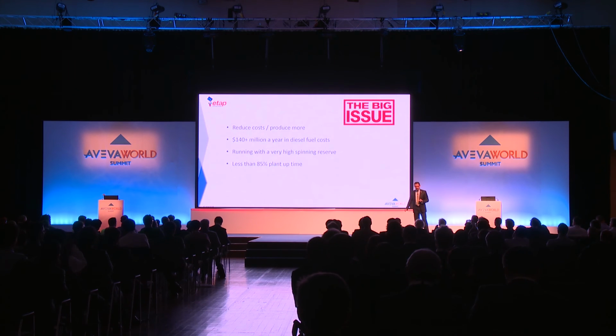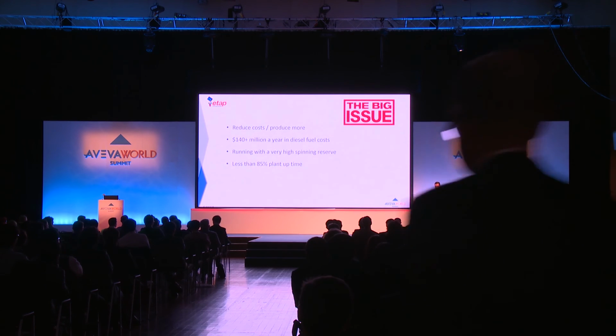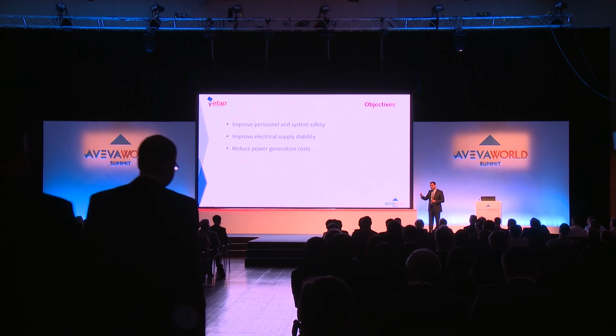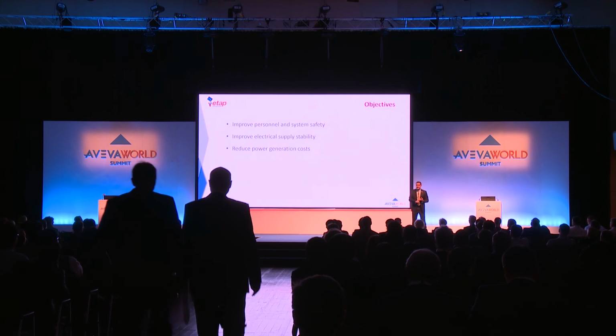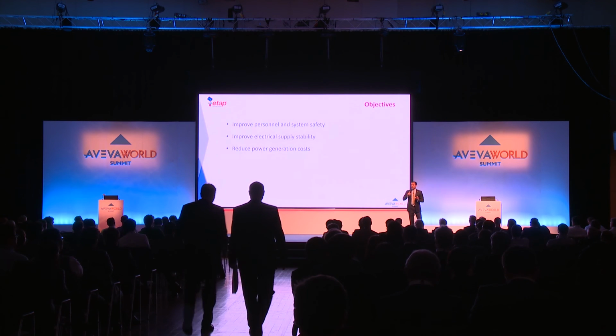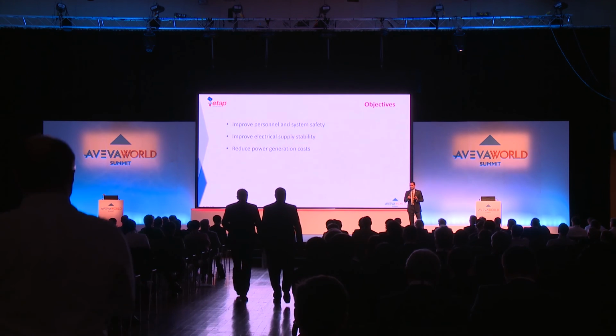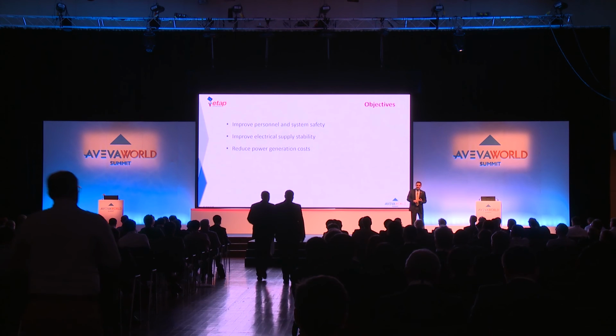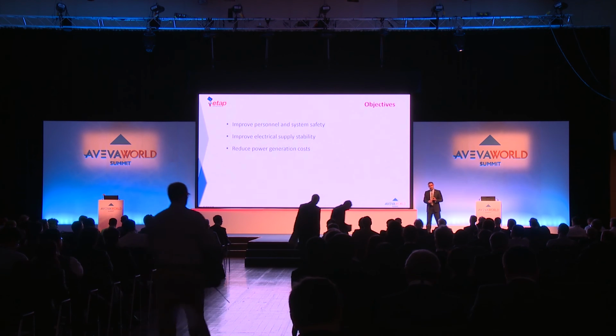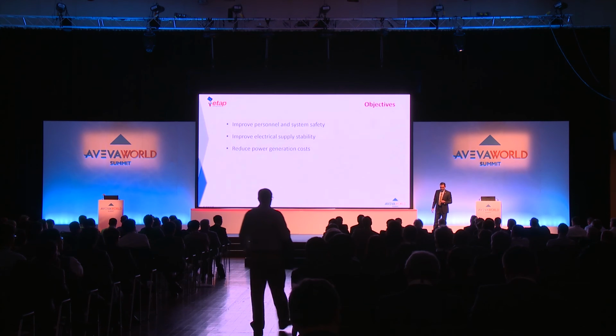The big issue for this client was reducing costs, produce more. Who doesn't have that issue? But in fact, one of the biggest problems was that they had more than $140 million worth of diesel fuel that they were using on a yearly basis. Their spinning reserve was high, and the reliability of the system was low. So the 3 main objectives started from the existing system: they needed safety improvements because of short circuit problems, arc flash problems, safety issues. Also improving the stability of the system and reducing the cost.